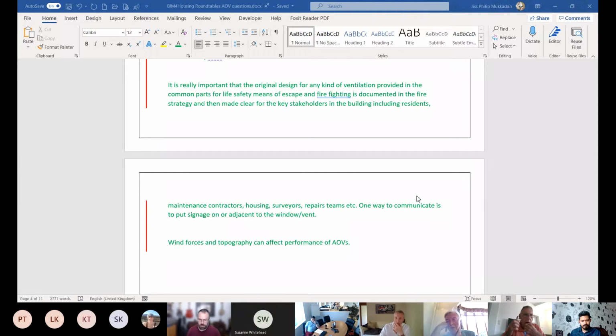Well, it's probably not inappropriate, Richard. It's that it's got a dual function, and therefore, okay. Yeah, it's probably got a dual function. Am I right on that, Edward? Well, yeah. I suppose the question is, should they have, or should we say it's only for the function of venting smoke? And if you want to get on the roof, create a separate hatch. That'd be my preference. You know what I'm going to say, don't you? Yeah, I know. I should have typed it first. No, not at all.